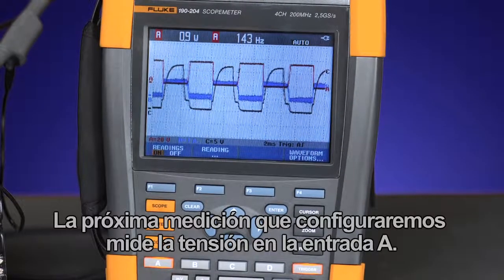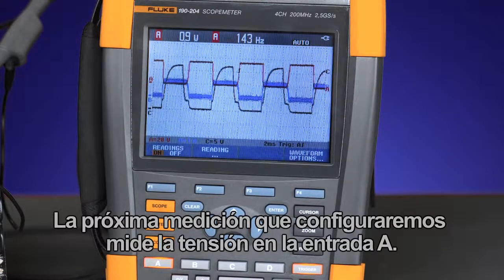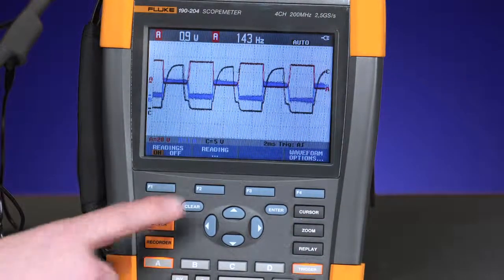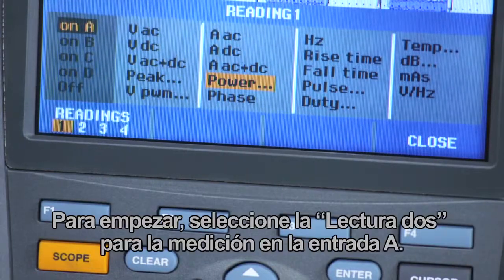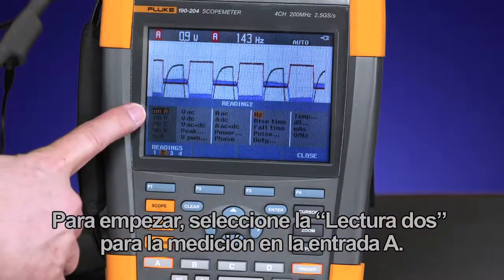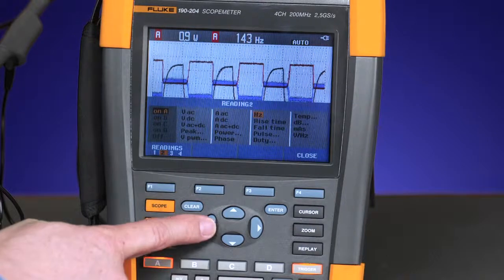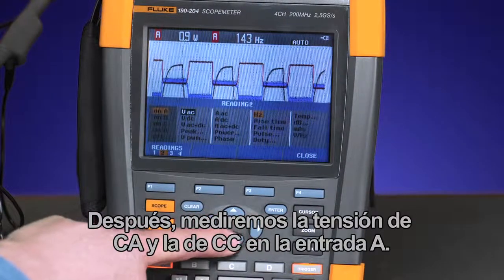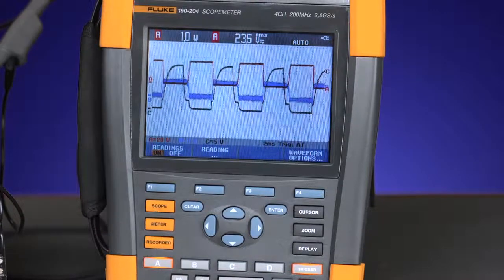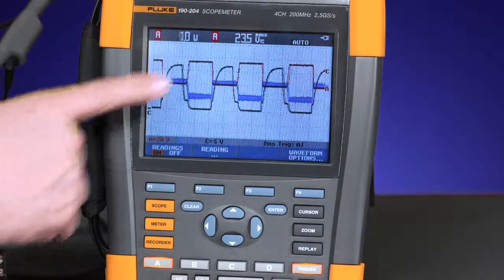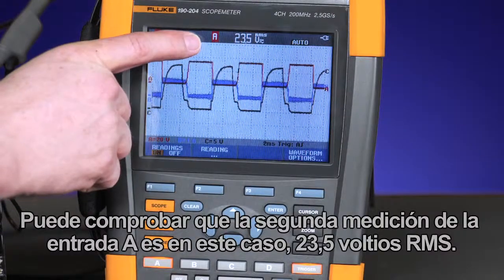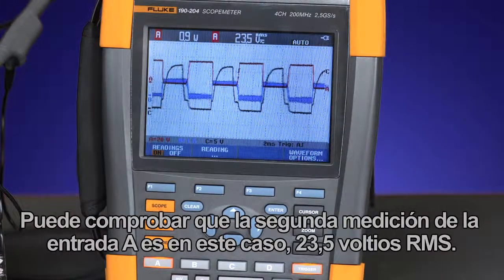The next measurement we'll set up measures the voltage on input A. To begin, select reading 2, measuring on input A. Next we'll measure the voltage AC plus DC across input A. You can see the second measurement on input A — in this case 23.5 volts RMS.